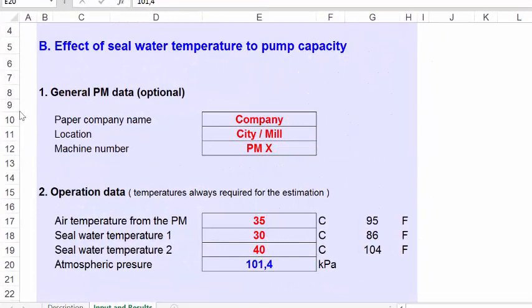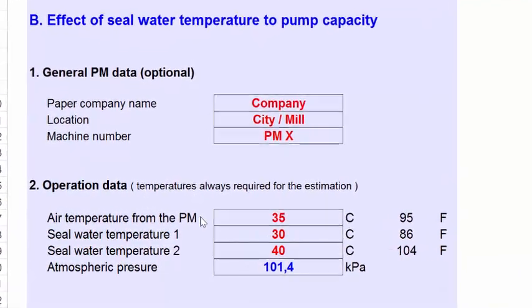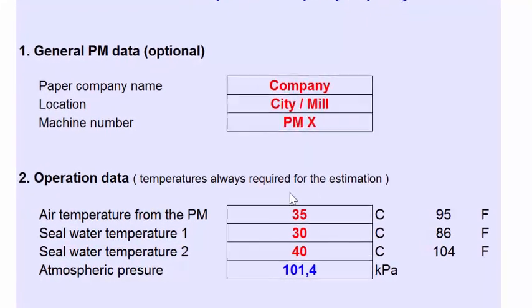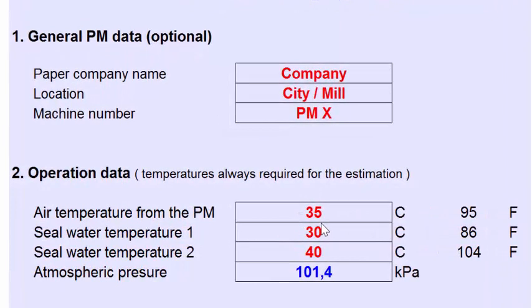Let's look at the required input data for the application. First, you can give general paper machine data if you want — that means paper machine name, location, and machine number. For the calculation, the following input data is required: the input temperature of the air from the paper machine. According to our measurements, it is normally between 33 and 40 degrees Celsius. In a typical case, 35 degrees Celsius (95 Fahrenheit) is a pretty good starting point for the calculation.